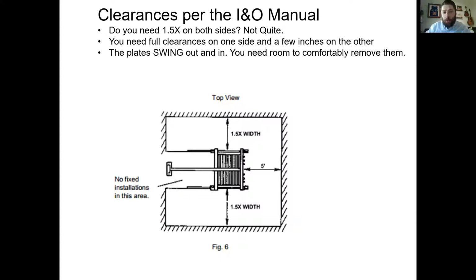So what clearances are required? Per the I&O manual, they're going to tell you you need 1.5 width of the entire unit on both sides. The back, you need to go to the end of that carry bar, as you can see, and you need 5 feet in the front, pretty much all the time. Do you really need 1.5 clearance? No, you don't. And this wouldn't be flagged by a building inspector either.